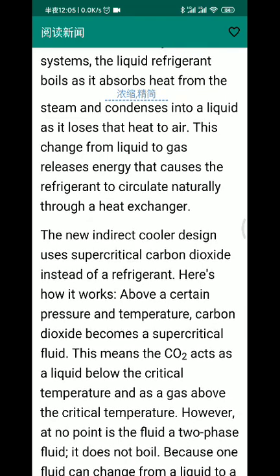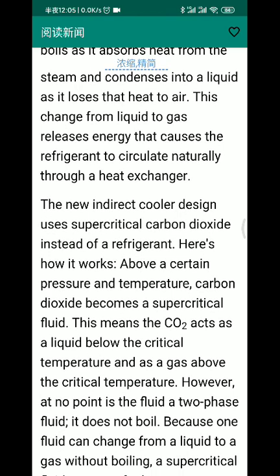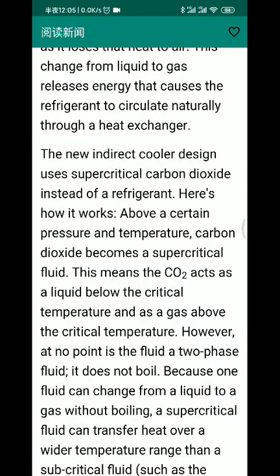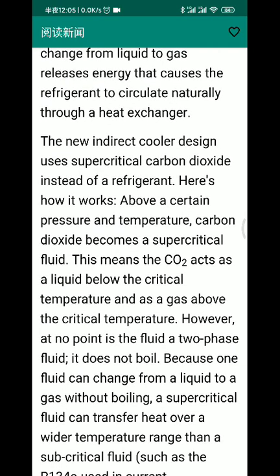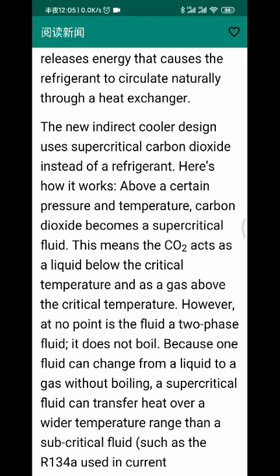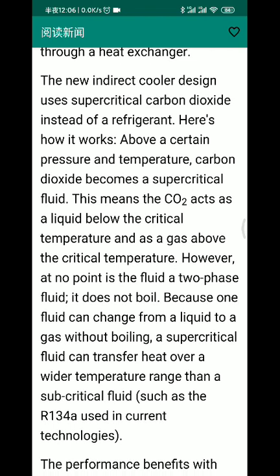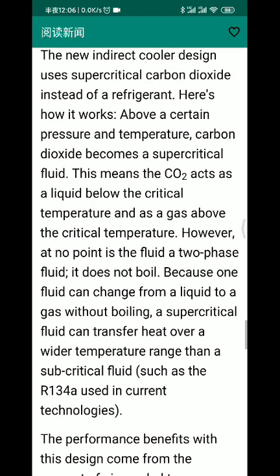The new indirect cooler design uses supercritical carbon dioxide instead of refrigerant. Here's how it works. Above a certain pressure and temperature, carbon dioxide becomes a supercritical fluid. This means the carbon dioxide acts as a liquid below the critical temperature and as a gas above the critical temperature. However, at no point is the fluid a two-phase fluid. It does not boil, because the fluid can change from a liquid to a gas without boiling. A supercritical fluid can transfer heat over a wider temperature range than a subcritical fluid, such as the R-134a used in current technologies.